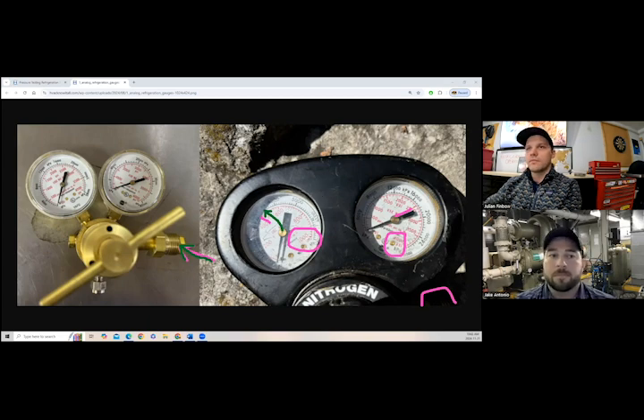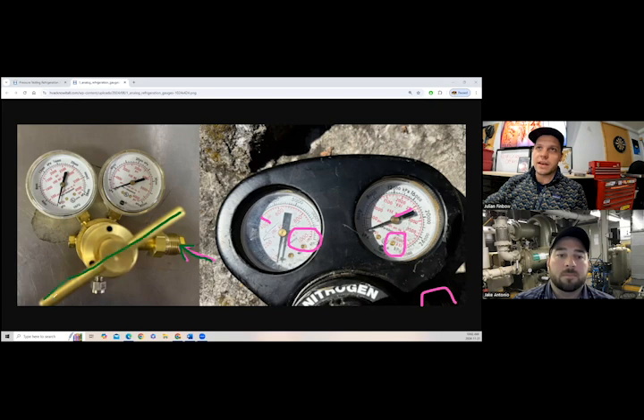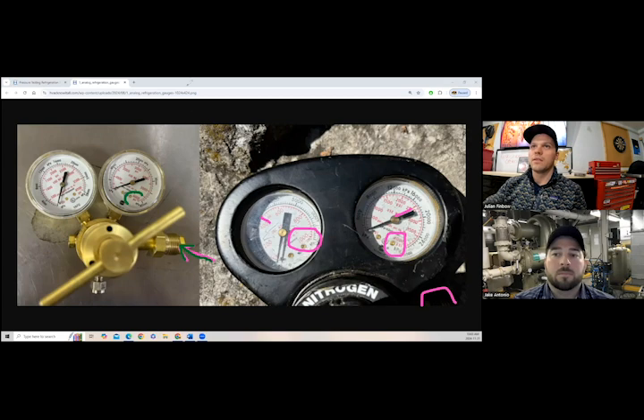And then to finish this, if we move over to the XPR regulator, we got a nice different style handle. You can take this off, so it's easy to store in your drawers. That's great. And then the bottle side is going to allow you to get 6,000 psi from the bottle if it goes up that high. So a high pressure bottle is going to be about 4,500 psig in a fresh bottle of high pressure nitrogen. So this is going to give you way more capacity to pressure test stuff than a bottle that's at like 2,500. Okay. And the face where you're going to put your pressure out, that fitting there, is going to be your outlet pressure. You have a way bigger range. So this face for the outlet goes up to 4,000 psig if you could ever get there.